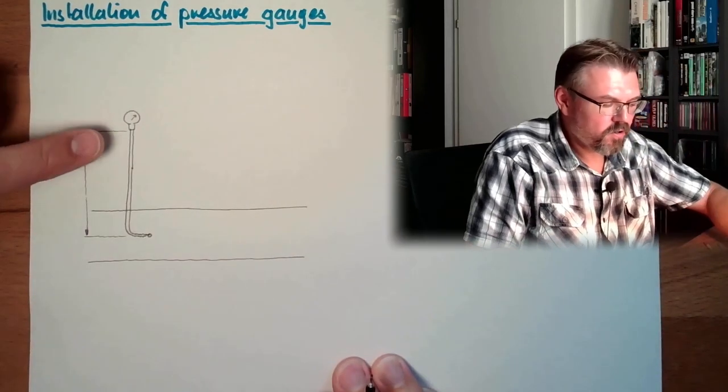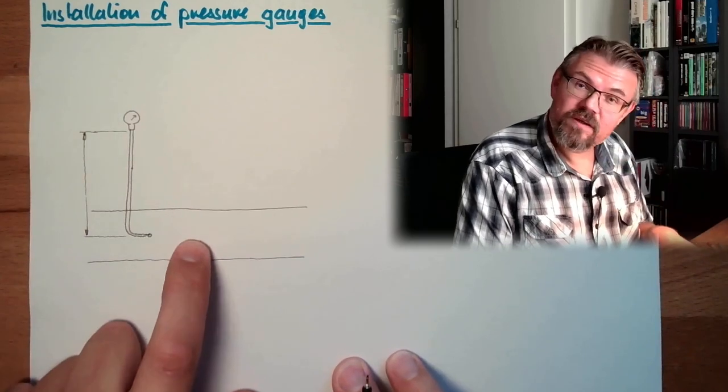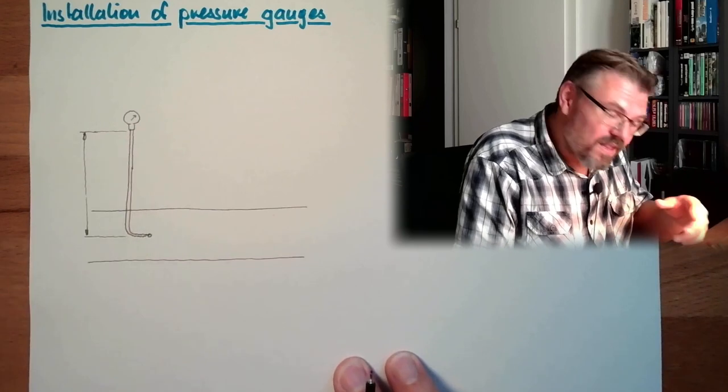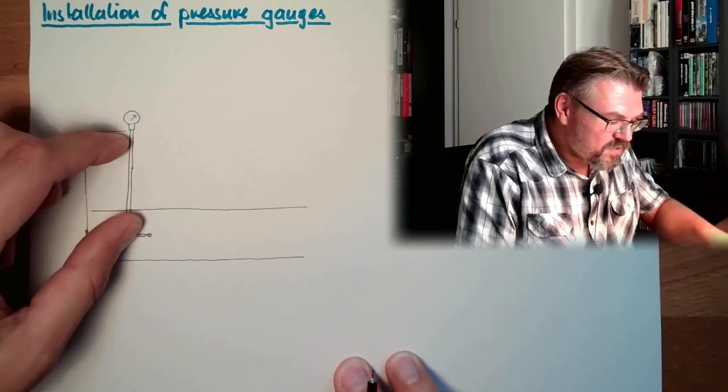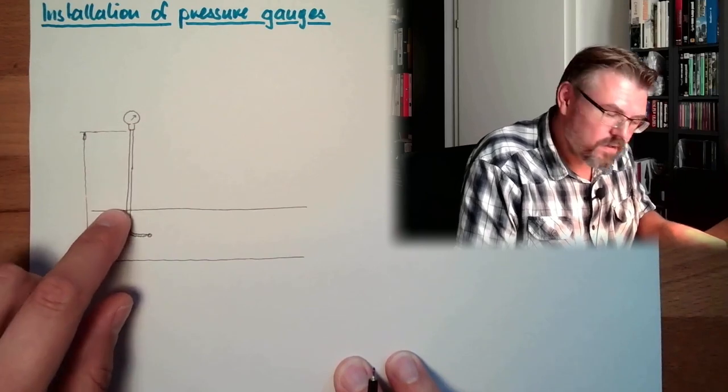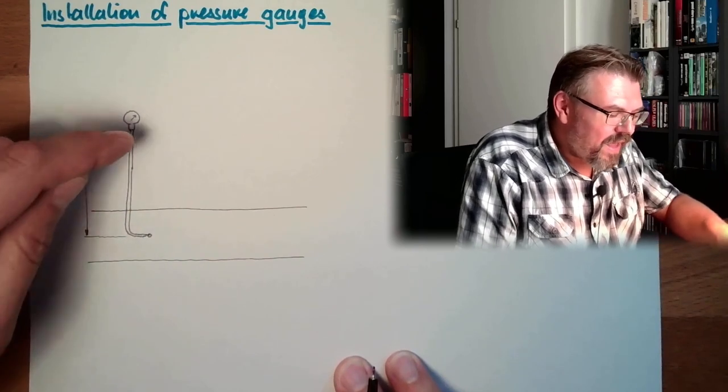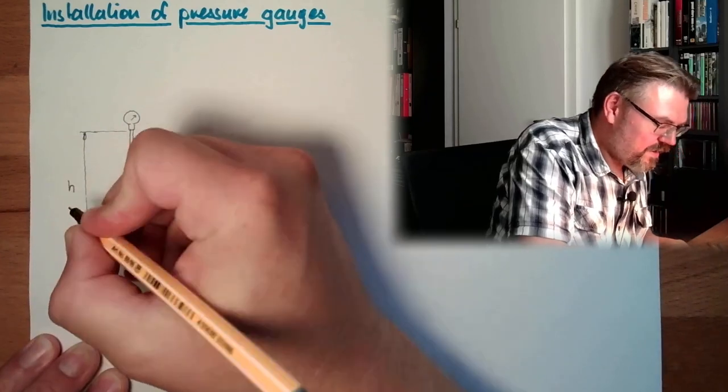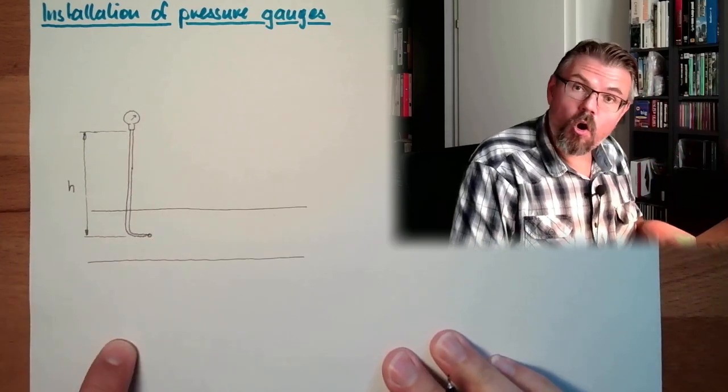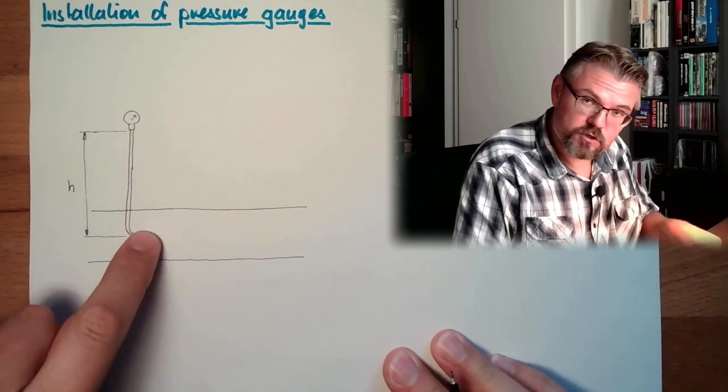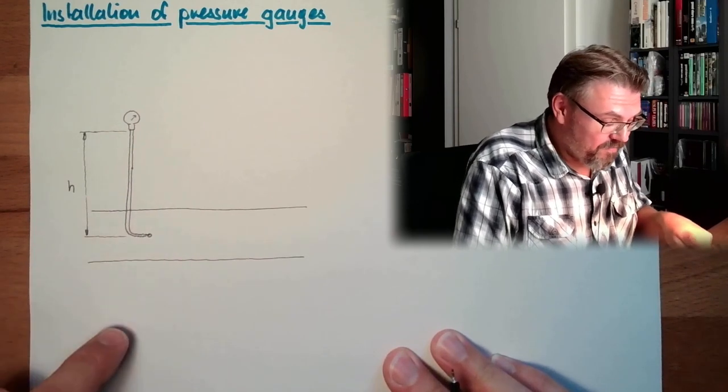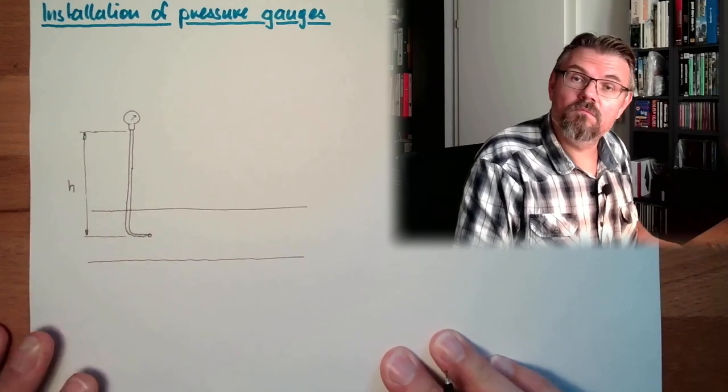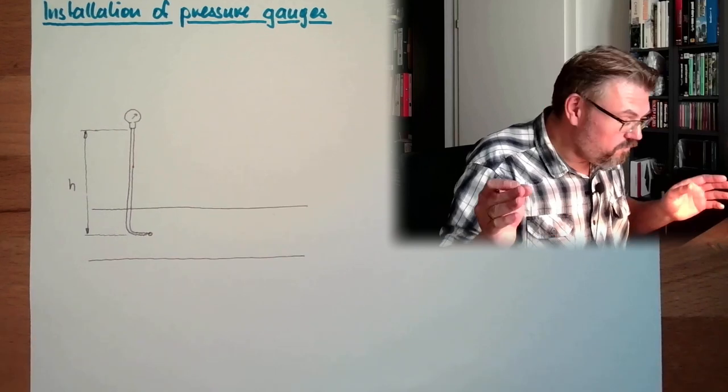This pressure gauge is showing less pressure than actually there is because there is water column, liquid column, gas column which have a certain weight and this weight will pull down. So I will have less pressure up here than here depending on the height. If I mount it below then I measure too much pressure because then I have the pressure here and I have the additional pressure of the weight of this column, whatever fluid this is.